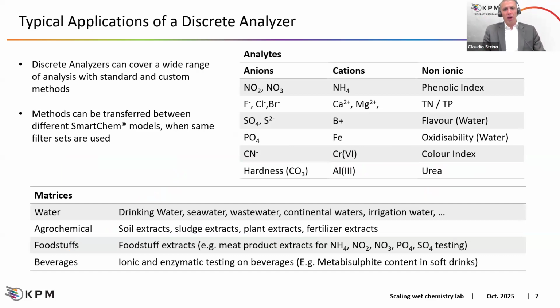A typical question is, what are the parameters, what are the matrices that we can analyze with the discrete analyzer? As we can see here, there is a huge panel of parameters. This is just an example of the most common methods, but there are also other parameters that can be tested. We can see anions, cations, and non-ionic parameters. And on different matrices: on water, all kinds of waters, drinking water, seawater, wastewater. Agrochemical testing means soil, sludge, plant, fertilizer extract, foodstuff. And one of the most common usages is the testing of multiple parameters on meat extracts, and also beverages. So we can have ionic and enzymatic testing, for example, on beer, on wine, and also on spirits.